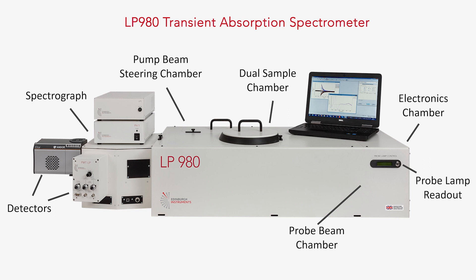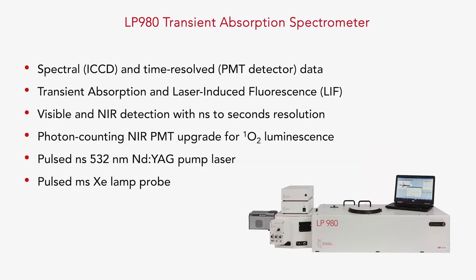In this investigation, we use the LP980 transient absorption spectrometer. This is a turnkey instrument for transient absorption and laser-induced fluorescence in the range of nanoseconds to seconds. The LP980 features an ICCD detector for spectral data and a PMT detector for time-resolved data. In this study, we used a photon-counting NIR-PMT in the detection arm of the spectrometer to measure singlet oxygen luminescence. The pump laser was a pulsed neodymium-YAG laser at 532 nanometers, and the probe was a pulsed xenon lamp.